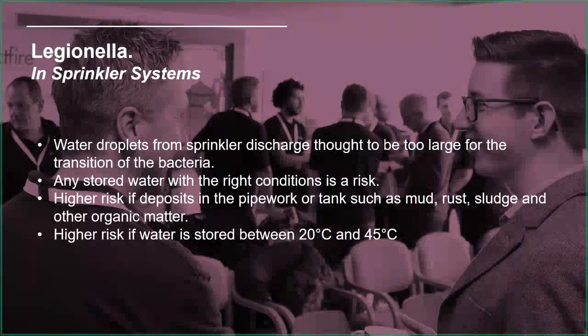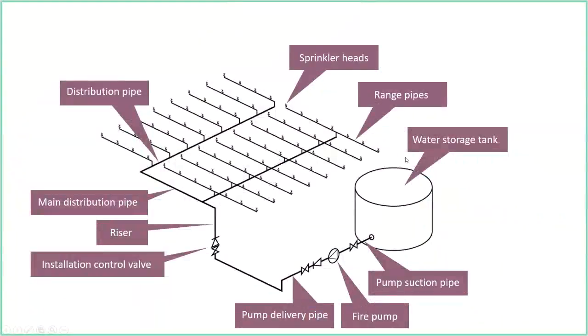There's also a higher risk if the water is stored between 20 and 45 degrees Celsius - that's the temperature which Legionella and the vast majority of bacteria like, being warm. For sprinkler systems, we're mostly storing the water below 20 degrees C, so the problem isn't completely gone, but it's vastly reduced. So for a sprinkler system, we've got our water storage tank - that's a potential risk of Legionella - and also the pipes themselves.